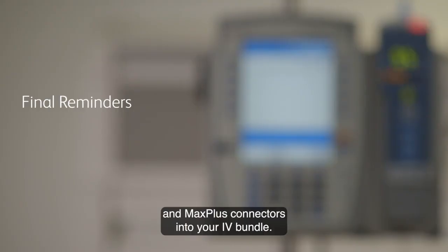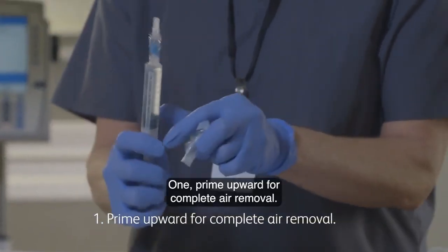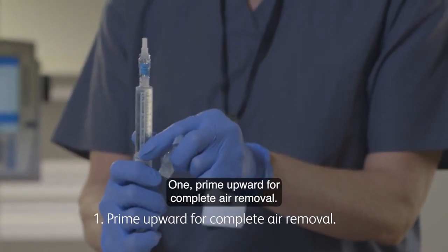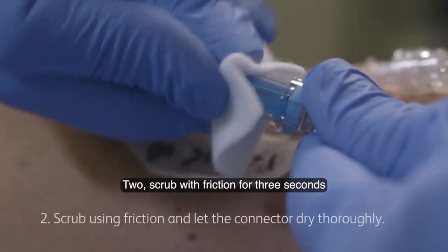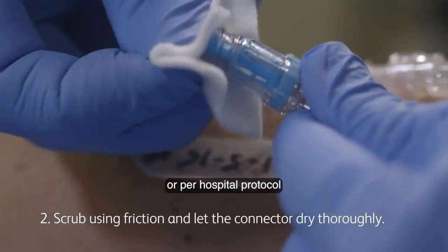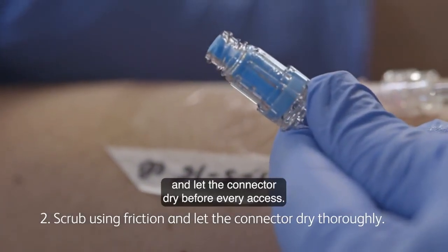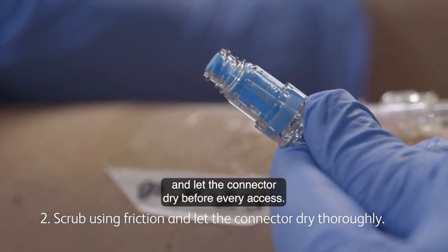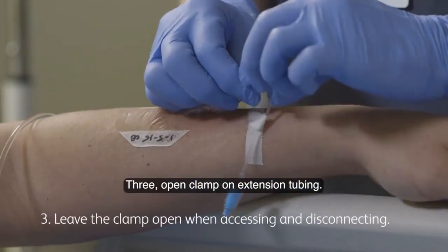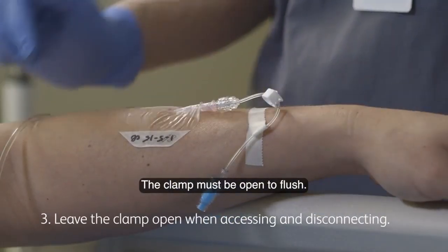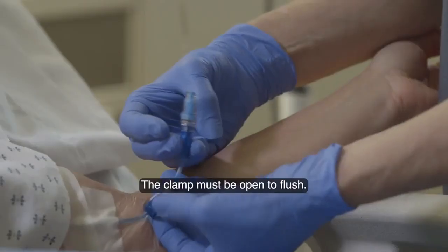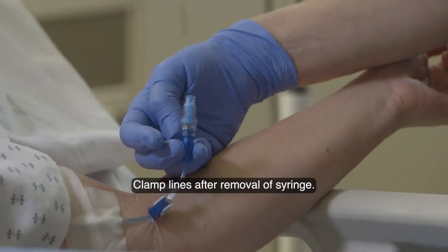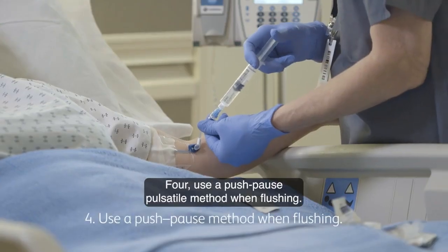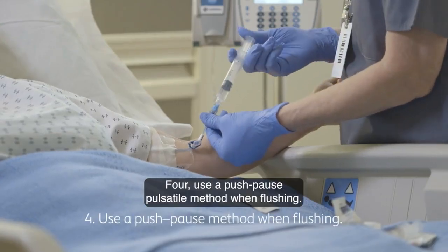Please consider the following reminders as you incorporate the MaxZero and MaxPlus connectors into your IV bundle. 1. Prime upward for complete air removal. 2. Scrub with friction for 3 seconds or per hospital protocol, and let the connector dry before every access. 3. Open clamp on extension tubing. The clamp must be open to flush. Clamp lines after removal of syringe. 4. Use a push-pause pulsatile method when flushing.